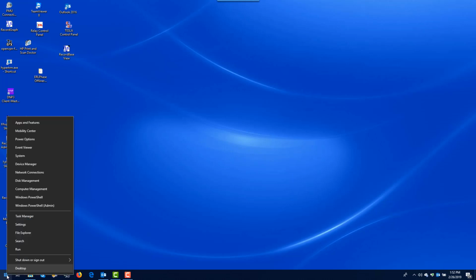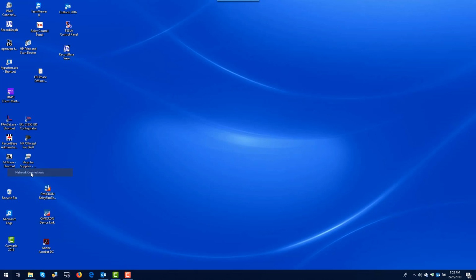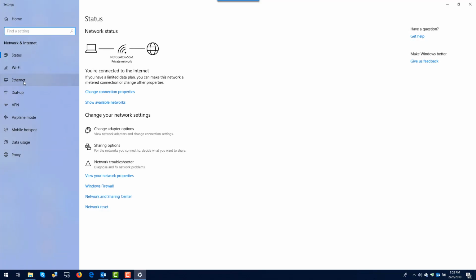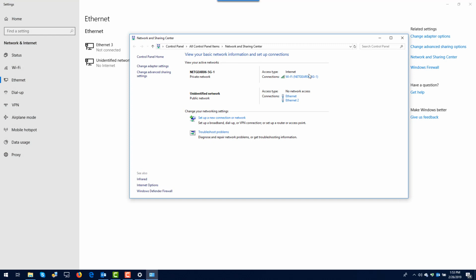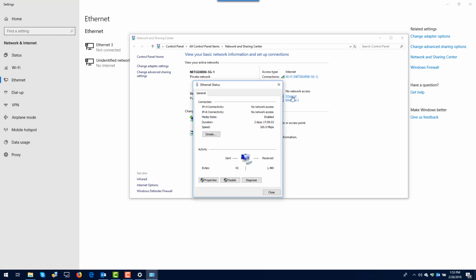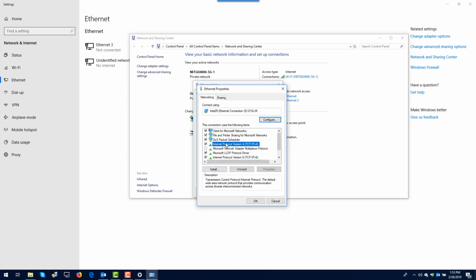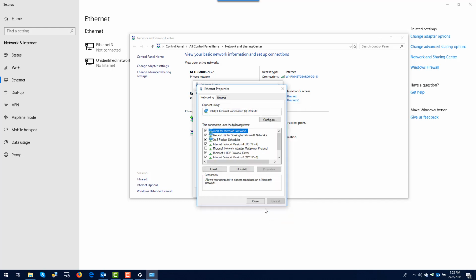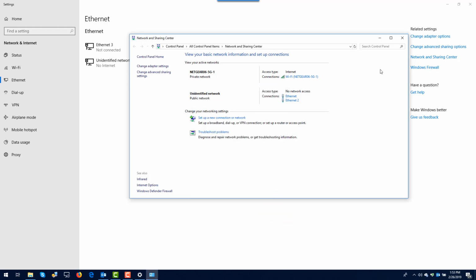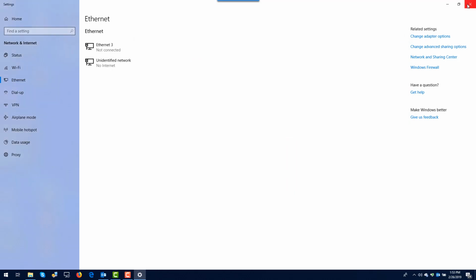In order to check your laptop IP address, you need to open your network connections and under the Ethernet selection, open up Network and Sharing Center. Click on the Ethernet option and open up the Properties tab. Double click on the Internet Protocol version 4 TCP/IPv4, then manually enter an IP address with the address 192.168.100.XX. Any node number other than 80, since that's the Tesla's default node number. You can now close your network configuration screen, and you should be able to use the Tesla control panel software to connect to the Tesla unit via Ethernet.